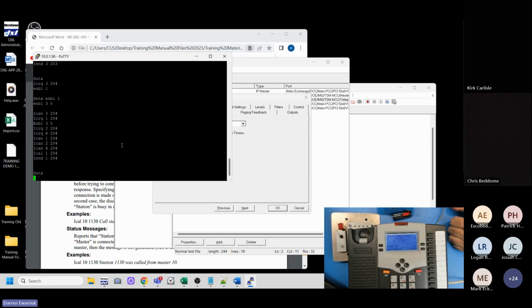So there's no conditionals in the configuration. The configuration only has, if this master is on, this master is secondary; it only has one secondary. So in the configuration, it can only go to one place, say, a floor master or a central master. But if you want to do something like this, and you have the ability to send commands, you can change on the fly, or at least temporarily, the secondary master for a master.